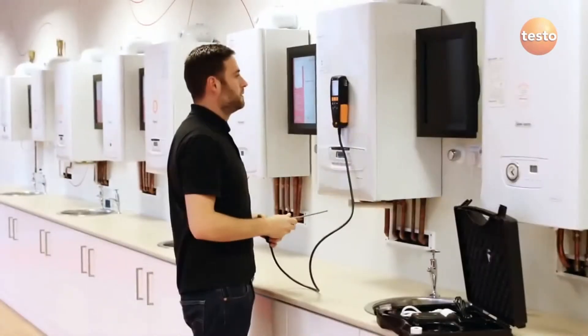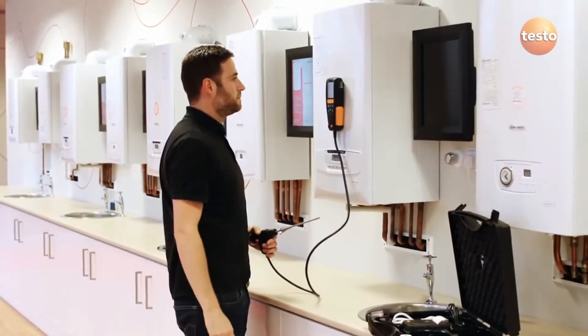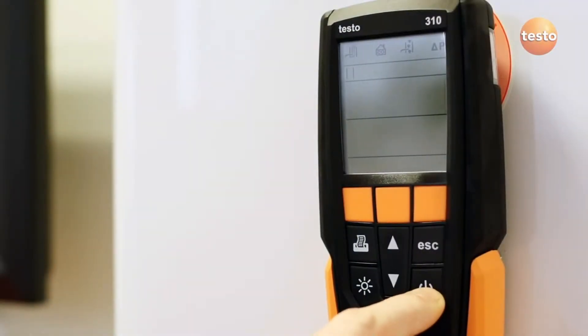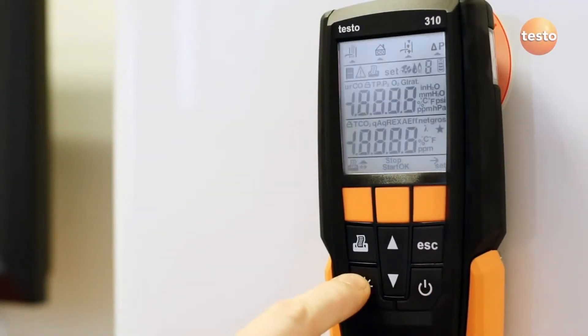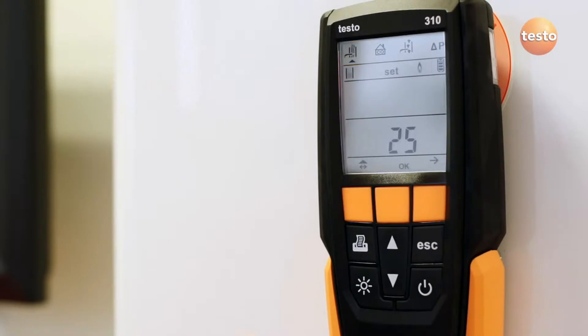The testo 310 is a flue gas analyzer for use in commissioning and servicing domestic boilers. To carry out a flue gas measurement, turn the instrument on and make sure the flue gas test icon is selected at the top of the screen. Then let the 310 zero the gas sensors with the probe in fresh air.